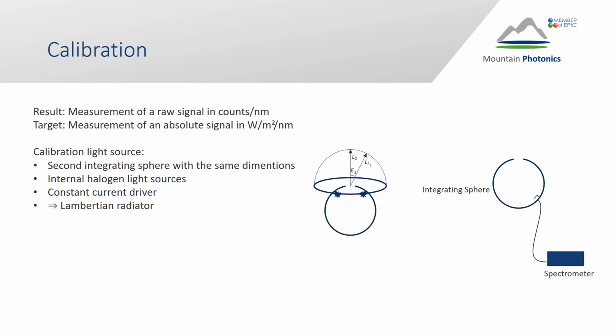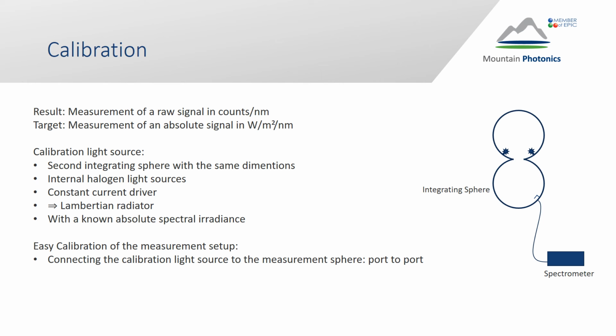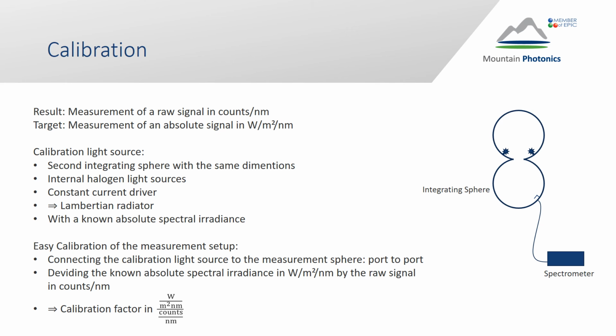And this gets us what we call a Lambertian radiator, with constant radiance independent of the angle at the exit port of the sphere. And of course we know the absolute spectral irradiance at the exit port of the sphere, so it's a calibrated light source. Well then, the calibration of the measurement setup is pretty easy. The only thing we have to do is to put this light source upside down on top of the measurement sphere, port to port, to get a well-known spectral irradiance at the entrance port of the measurement sphere. And then we have to measure this irradiance with the raw signal of the spectrometer and divide the well-known absolute spectral irradiance by this raw signal. And this gets us the calibration factor in watt per square meter and nanometer divided by counts per nanometer.